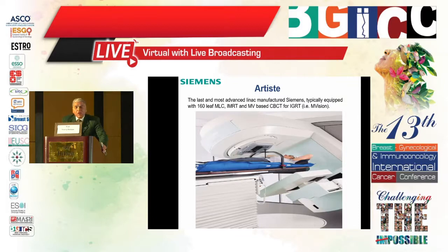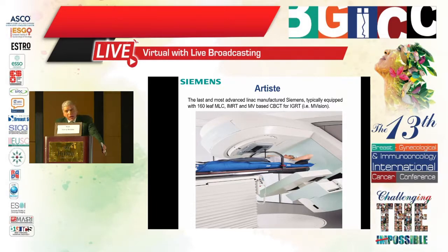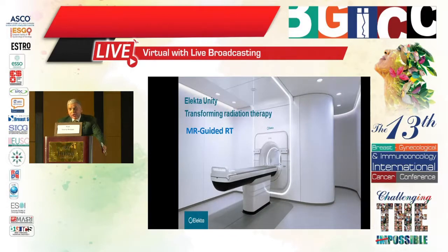One of the latest Siemens machines — Siemens stopped manufacturing linear accelerators five or six years ago. The last model was the Artiste, of which we have a couple at the Alexandria Radiotherapy Oncology Center. It offers 160-leaf multi-leaf collimator IMRT, cone-beam CT for IGRT, and MVision imaging — and it is very effective.